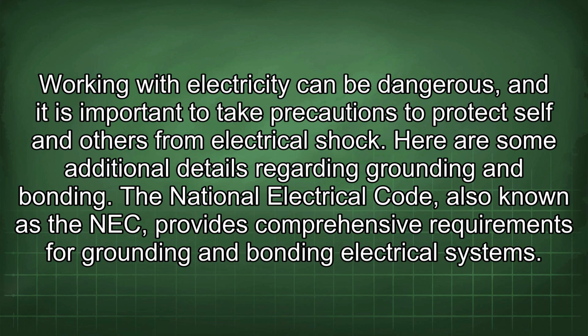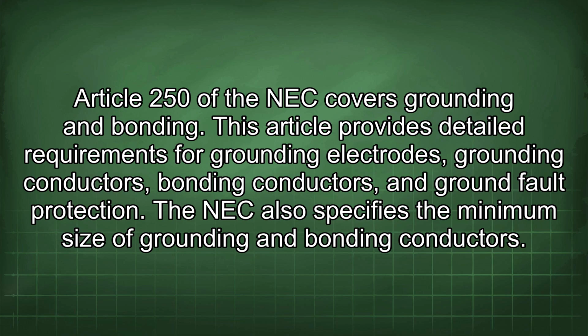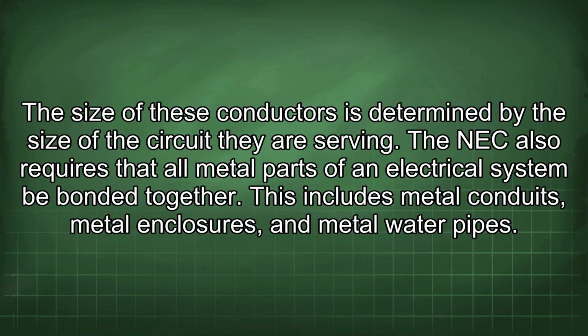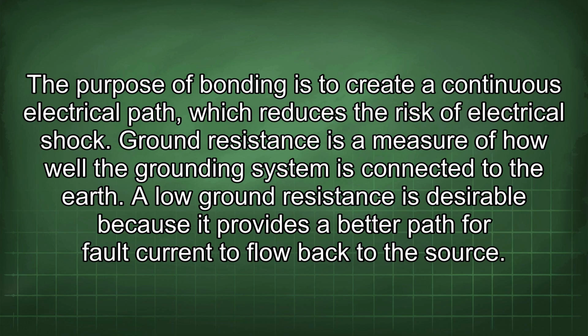The National Electrical Code, also known as the NEC, provides comprehensive requirements for grounding and bonding electrical systems. Article 250 of the NEC covers grounding and bonding. This article provides detailed requirements for grounding electrodes, grounding conductors, bonding conductors, and ground fault protection. The NEC also specifies the minimum size of grounding and bonding conductors. The size of these conductors is determined by the size of the circuit they are serving. The NEC also requires that all metal parts of an electrical system be bonded together. This includes metal conduits, metal enclosures, and metal water pipes. The purpose of bonding is to create a continuous electrical path, which reduces the risk of electrical shock.